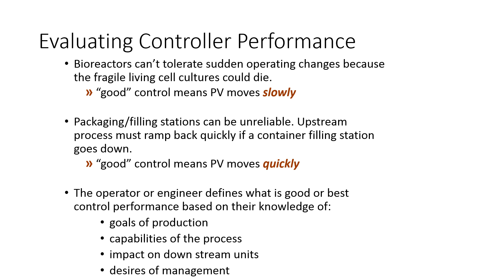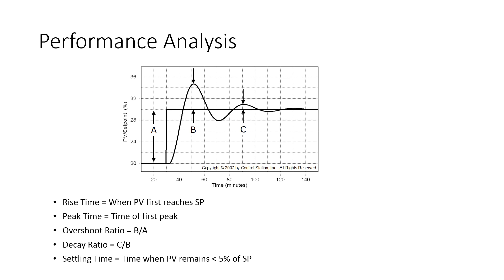One of the things we want to also talk about is controller performance, not just tuning these PI controllers. We want to try to understand what is good performance for a PI controller. And we're going to just use a couple pieces of terminology here. First of all, we have rise time. When the PV, so this is our PV, and then this is our set point. From the time of the step, that's going to be 30, to when the PV first reaches the set point.